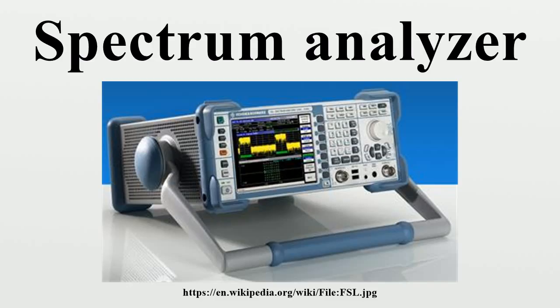Detector. With the advent of digitally based displays, some modern spectrum analyzers use analog-to-digital converters to sample spectrum amplitude after the VBW filter. Since displays have a discrete number of points, the frequency span measured is also digitized. Detectors are used in an attempt to adequately map the correct signal power to the appropriate frequency point on the display. There are in general three types of detectors: sample, peak, and average.